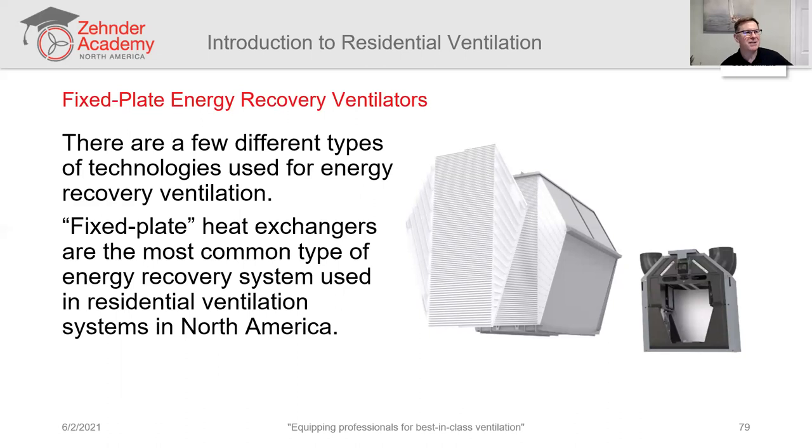There are a few different types of energy recovery technologies. The most common used in North American homes is fixed plate recovery ventilation systems. These fixed plates are stacked one on top of each other to basically form sort of a heat exchanger, almost a radiator in a way. And both outdoor supply air and indoor exhaust air are passed through this heat exchanger.